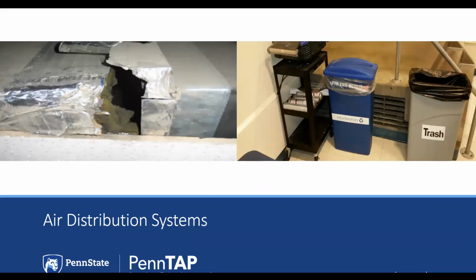Indoor air quality is a growing topic in schools and is part of all sustainability conversations. Make sure you take a moment to put eyes on your air distribution systems to confirm the conditions of the ductwork, exhaust fans, and dampers. 10 to 30% of conditioned air is wasted due to leaks. Make sure you don't have any blockages in the ductwork or in front of your vents. Indications that you're having issues with your air ducts include mold, sewage gas, exhaust fans not operating as they should, stuffiness, and other odors. Also consider condensation on windows, and if it's winter, you can see if you have quick-melting snow on the roof or a warmer attic or crawl space.